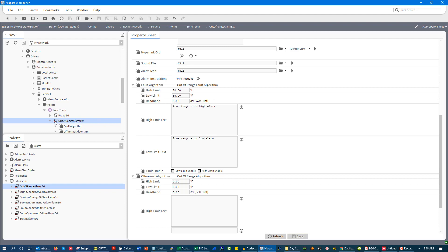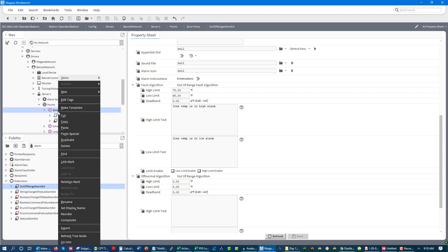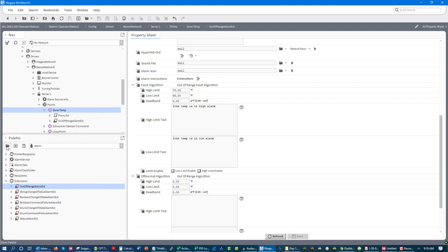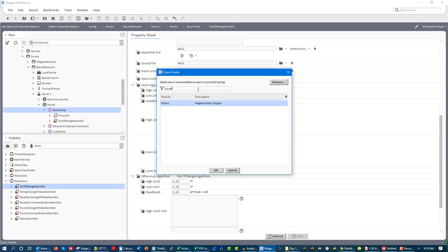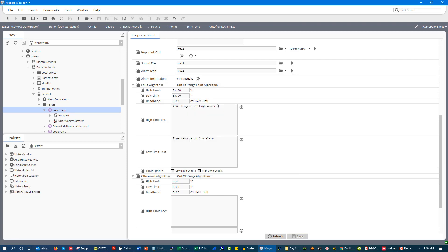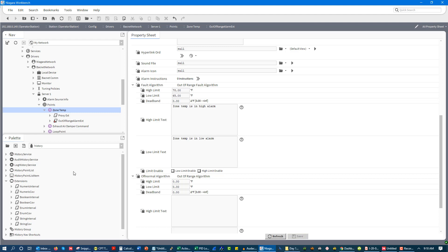And then when you have alarms, you'll have an alarm dashboard that then can show, hey, these alarms are occurring. What I can also do is I can go for this and I can go to my history, which in other software is known as trends. But I can go to my history, I can go to my extensions, and I can go to either an interval or a change of value. Interval is time-based. Change of value is when the value changes by a certain amount.